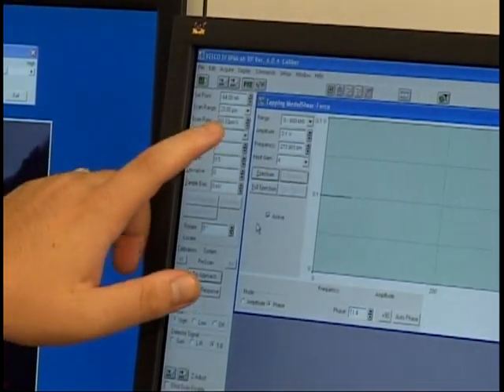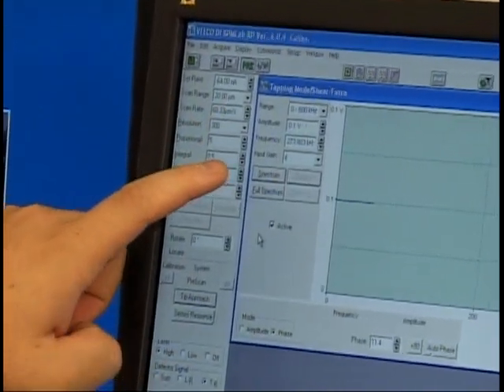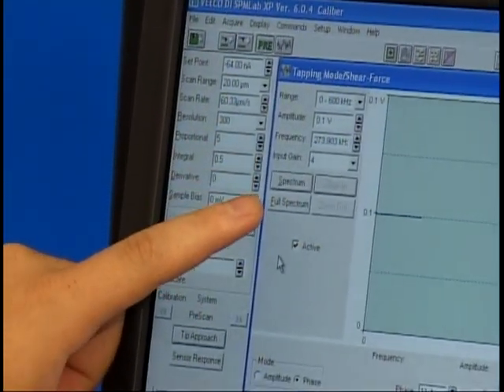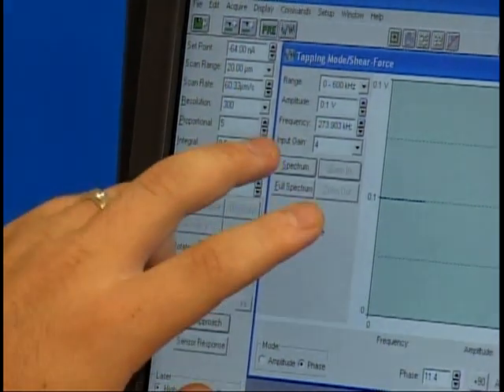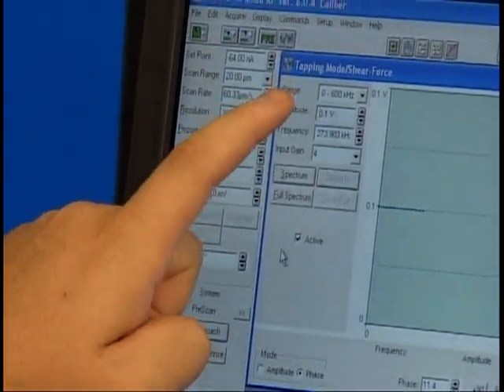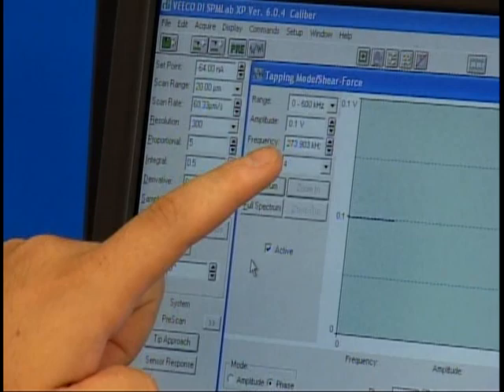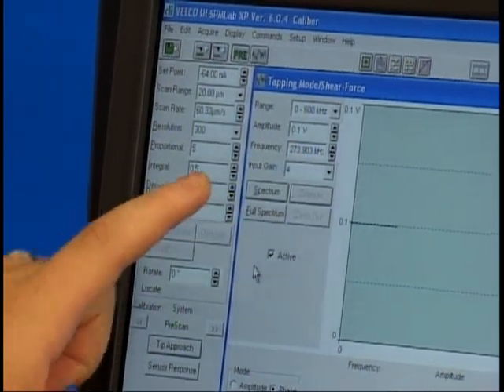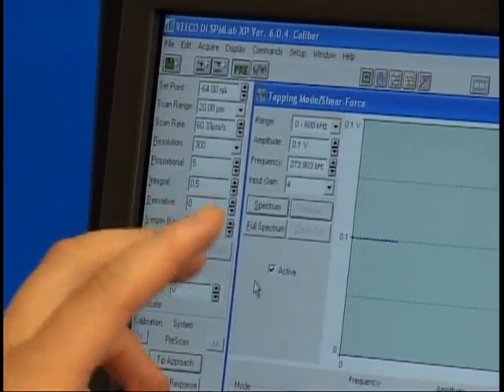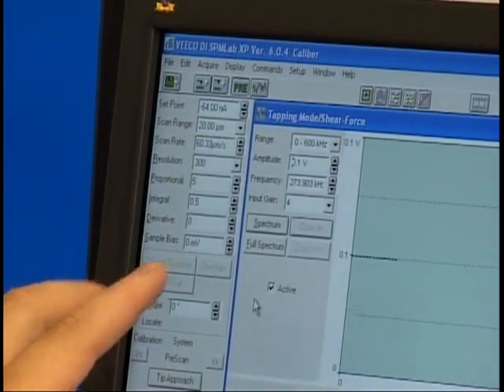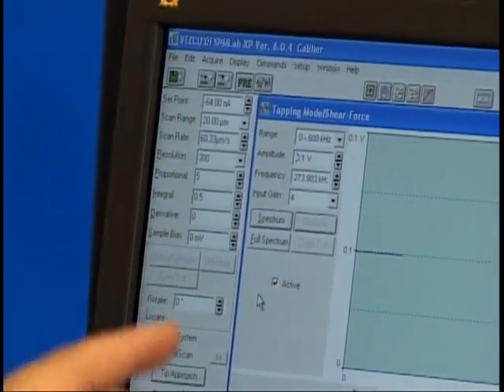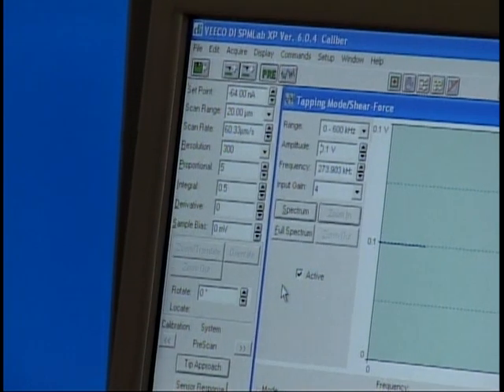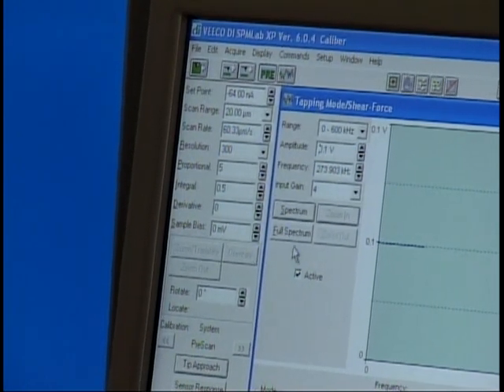Now, there's two buttons you can select, spectrum and full spectrum. Full spectrum will run the full range that you have selected before, 0 to 600 kilohertz right now. If we zoom in into a specific range, you would only select spectrum, and it will only sweep that specific range that you zoomed in on. So right now we'll do a full spectrum.